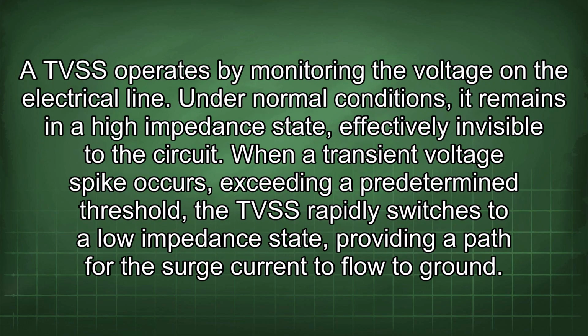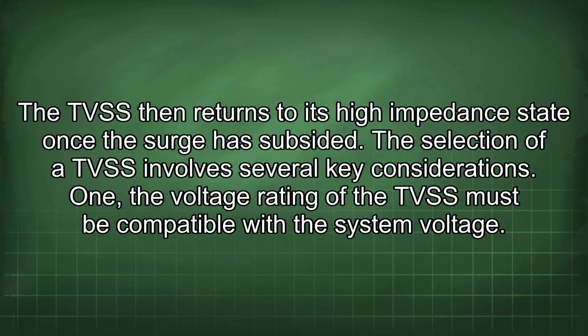A TVSS operates by monitoring the voltage on the electrical line. Under normal conditions, it remains in a high impedance state, effectively invisible to the circuit. When a transient voltage spike occurs exceeding a predetermined threshold, the TVSS rapidly switches to a low impedance state, providing a path for the surge current to flow to ground. The TVSS then returns to its high impedance state once the surge has subsided.